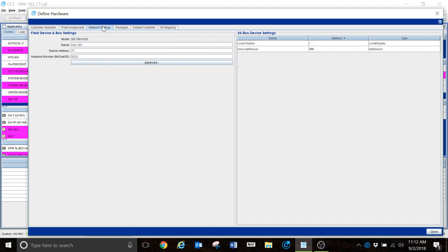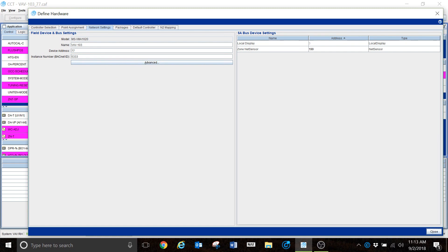Our network settings is going to be our third tab here. CCT is very network sensitive. This particular device address — whatever you have those jumpers set for inside that controller for your network settings, whether it's on a BACnet network or N2, this needs to match. If it does not match, you're not going to be able to load this controller — it will not let you. That way it helps ensure you don't load the wrong program into the wrong controller. So if you have a VAV addressed at 77, you need to set this device address here at 77; if you address your VAV 25, this needs to be at 25 also.